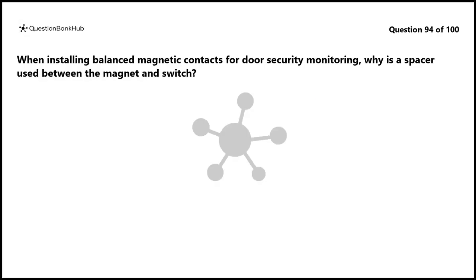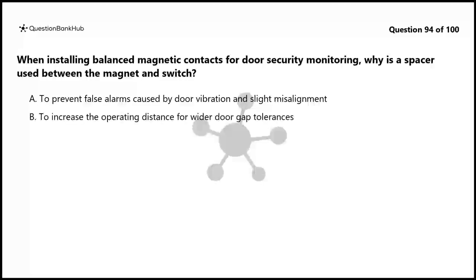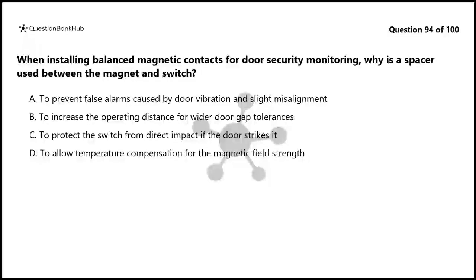Question 94. When installing balanced magnetic contacts for door security monitoring, why is a spacer used between the magnet and switch? A. To prevent false alarms caused by door vibration and slight misalignment. B. To increase the operating distance for wider door gap tolerances. C. To protect the switch from direct impact if the door strikes it. D. To allow temperature compensation for the magnetic field strength.